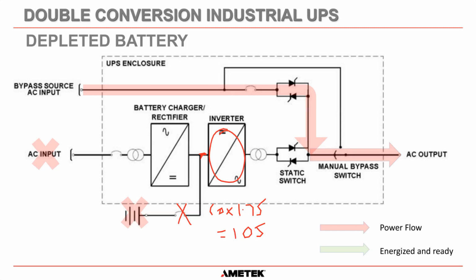Okay, but our inverter is clever enough, before it trips this breaker here, it says, okay, well, what we need to do before we trip that breaker, we need to transfer over to bypass. So we turn this static switch on, we turn this static switch off, and there is an overlap. When we turn the bypass static switch on, it is on at the same time as the inverter static switch is on for half a cycle. And then the inverter static switch turns off. So it is a seamless transfer to bypass. And then we trip the battery input breaker. That way we can guarantee that your AC load circuits continue to be powered, and they will not notice that there has been any change inside the UPS whatsoever. Your load circuits will be maintained throughout this process.